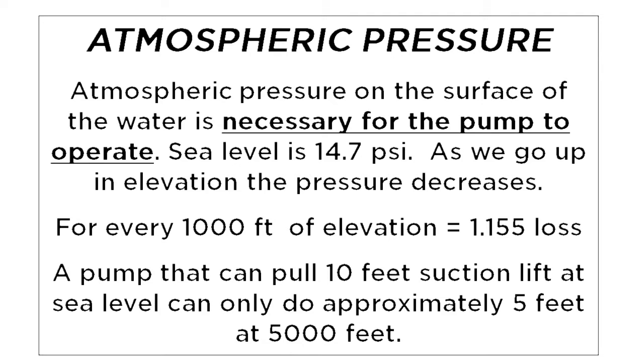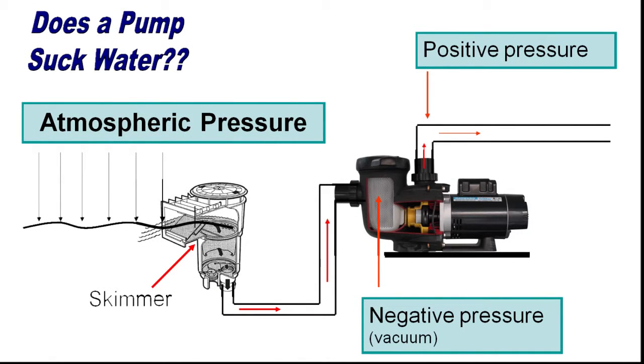Atmospheric pressure on the surface of water is necessary for a swimming pool centrifugal pump to operate. At sea level, the pressure is 14.7 PSI. As we go up in elevation, the pressure decreases. A pump that can pull water up 10 feet at sea level can only do approximately 5 feet at 5,000 feet of altitude. Since we're talking about atmospheric pressure, let's explain how water gets from the pool to the pump. We're going to dispel the notion that pumps suck water.